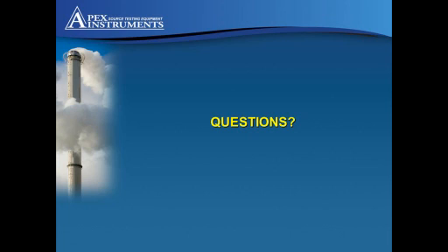That would then lead on to another question that we did receive: what is the probe length required for PS12B? That might be coming from some feedback that we've had that I'm not sure if you are aware of, but Method 30B does have a specific statement in that legislation that says you must be testing within the centroidal area of the stack to perform your 30B testing. However, I'll hand it over to Chris to speak more on the PS12B testing area in the stack.